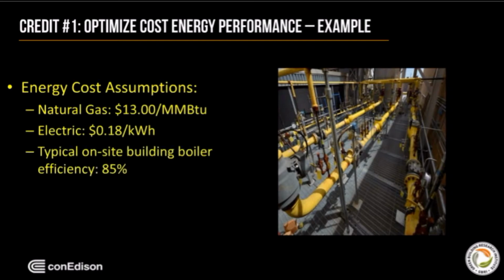Assuming, since prices fluctuate, that natural gas is $13 per million BTU, based on average general rates reported by our gas department and steam department at Con Edison, and that electricity is 18 cents per kilowatt hour, and assuming we're comparing Con Edison's CHP system to a typical site boiler with an 85% efficiency, we can proceed with the following calculation.